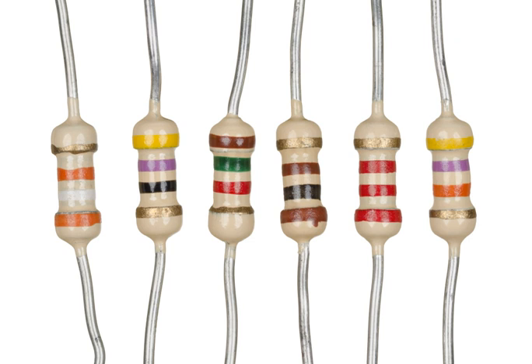Since 1990, the international resistance standard has been based on the quantized Hall effect discovered by Klaus von Klitzing, for which he won the Nobel Prize in Physics in 1985. Resistors of extremely high precision are manufactured for calibration and laboratory use. They may have four terminals, using one pair to carry an operating current and the other pair to measure the voltage drop. This eliminates errors caused by voltage drops across the lead resistances, because no charge flows through voltage sensing leads. It is important in small value resistors, 100 to 0.0001 ohm, where lead resistance is significant or even comparable with respect to resistance standard value.